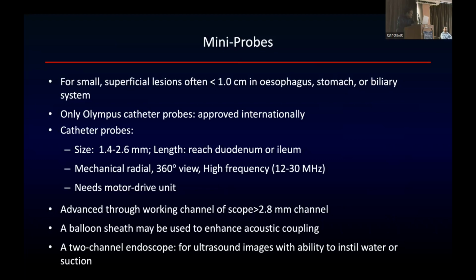It's a mechanical radial one, 360-degree field of view, high frequency. So that's the difference. So you are able to get a better resolution. As I mentioned, as the frequency increases, the resolution of the wall layers of the structure near to the probe improves. So this is what it does. If you see, the frequency is up to 30 megahertz, so very high frequency. So if you want to see a structure which is very nearby, you place a probe just near to it, and you have a very good resolution of this. Again, it needs a motor-driven unit.